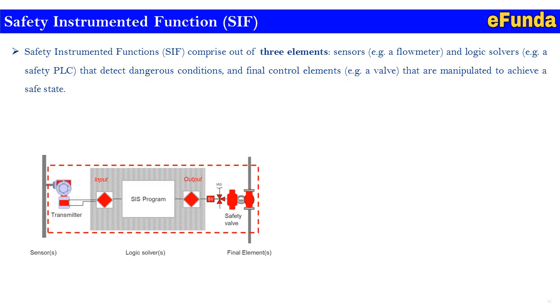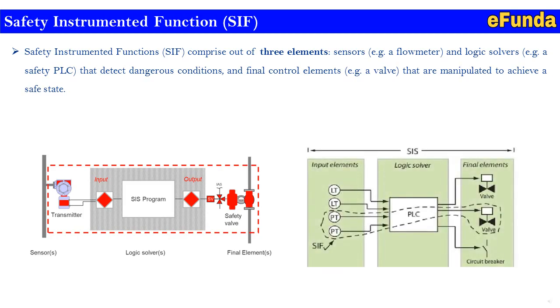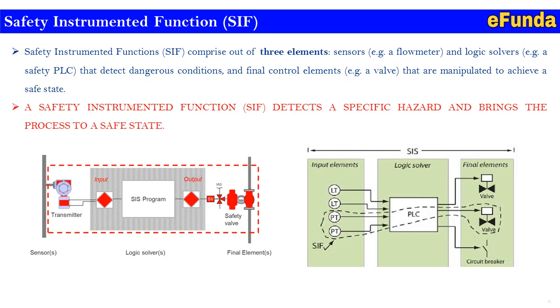In another diagram, the SIS arrangement shows various field devices connected as inputs to a logic solver (PLC), which then drives the final elements (valves). Pressure transmitters (PTs) falling under the SIS functions and the loop arrangement are also illustrated. A Safety Instrumented Function always detects a specific hazard and brings the process to a safe state. This is how the SIF is useful when implementing or designing a Safety Instrumented System.